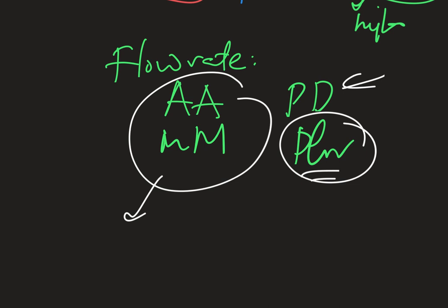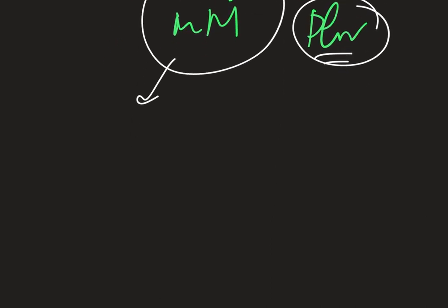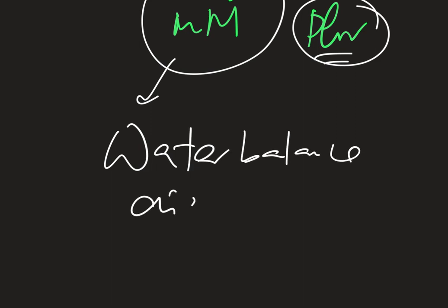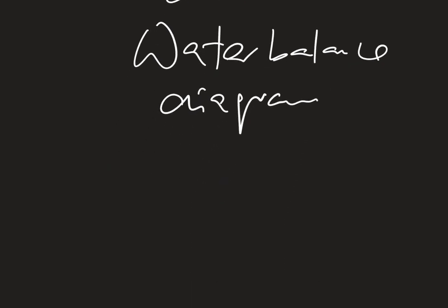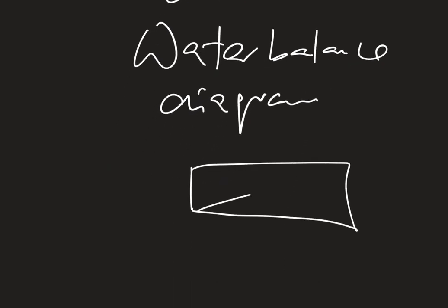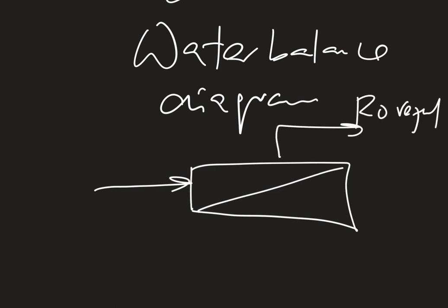For industrial wastewater we have a similar scheme as well, but normally it is very complicated, so we need to have a water balance diagram. From this water balance diagram, you will know, for example, that if I need to do water recovery, I have an RO system. RO reject going to the sea, the COD cannot be more than 100 ppm. But normally you have high chloride, so your COD reading will be affected.